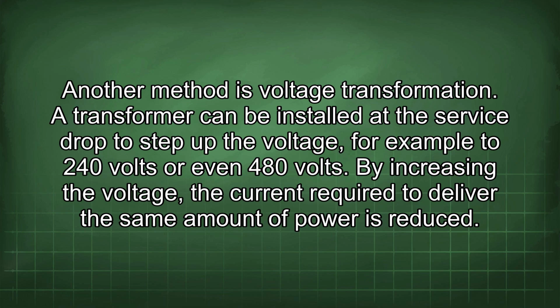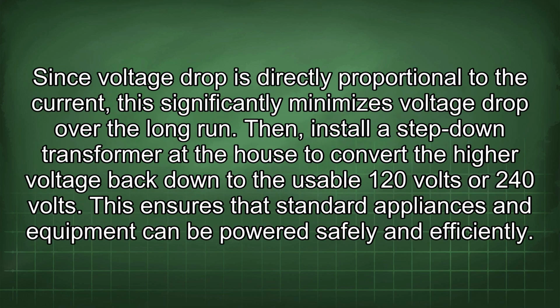Another method is voltage transformation. A transformer can be installed at the service drop to step up the voltage, for example to 240 volts or even 480 volts. By increasing the voltage, the current required to deliver the same amount of power is reduced. Since voltage drop is directly proportional to the current, this significantly minimizes voltage drop over the long run. Then, install a step-down transformer at the house to convert the higher voltage back down to the usable 120 volts or 240 volts. This ensures that standard appliances and equipment can be powered safely and efficiently.